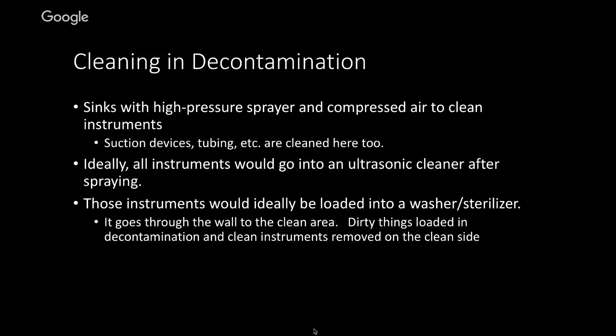So here's kind of an example here. The decontamination is that horizontal area just below the midline there, and you can see the various equipment and supplies and hoppers and so forth that are listed there. The one thing between the decontamination and sterilization is that there should actually be a half door right there. It looks like kind of a wall, but it's not really. It's a half door. You don't want people walking from sterilization into decontamination area. You don't want people from decontamination walking into the sterilization area.